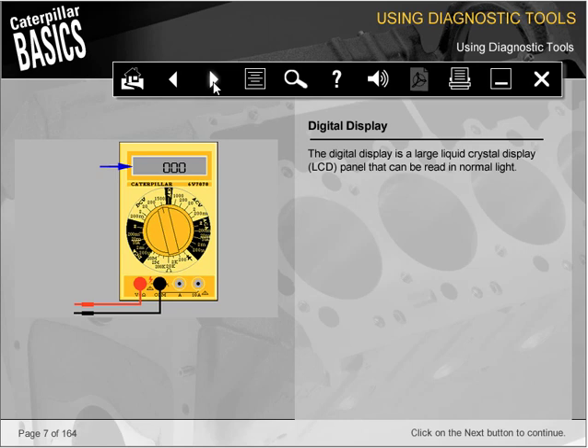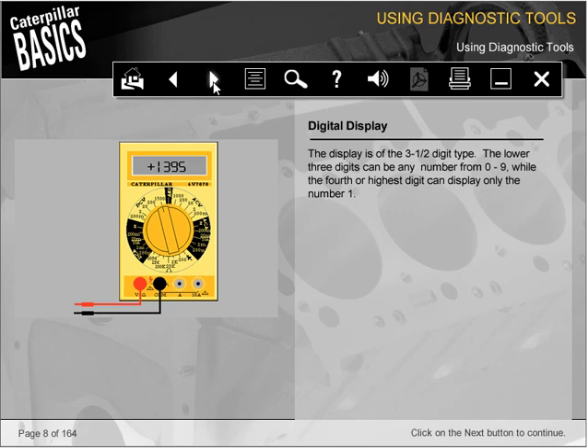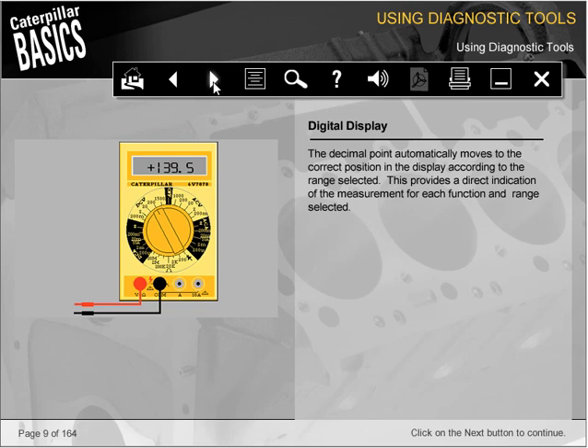The digital display is a large liquid crystal display, LCD, panel that can be read in normal light. The display is of the 3 1/2 digit type. The lower 3 digits can be any number from 0 to 9, while the 4th or highest digit can display only the number 1. The decimal point automatically moves to the correct position in the display according to the range selected. This provides a direct indication of the measurement for each function and range selected.